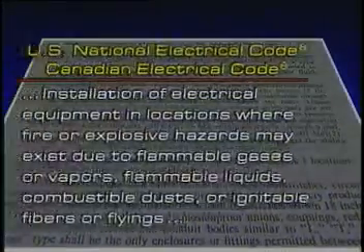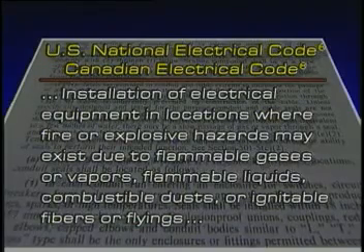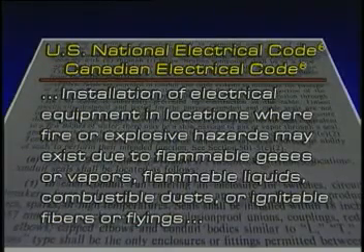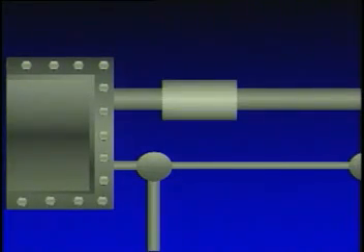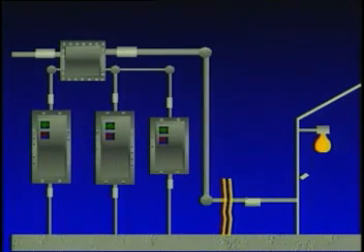The U.S. National Electrical Code and Canadian Electrical Code describe the requirements for the installation of electrical equipment in locations where fire or explosive hazards may exist. Both codes require that explosion-proof enclosures housing arcing and sparking devices be sealed off to prevent propagation of flames or gases through the conduit system and to minimize explosion pressures.